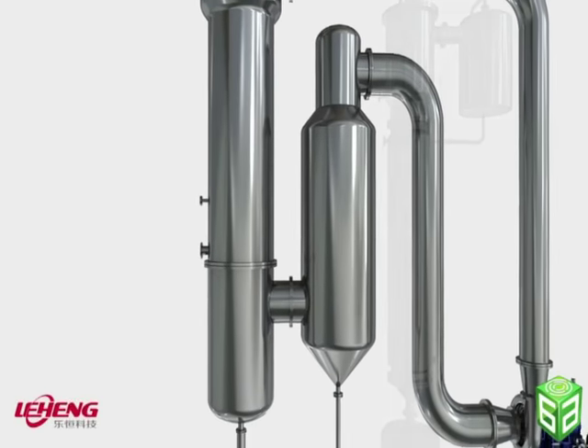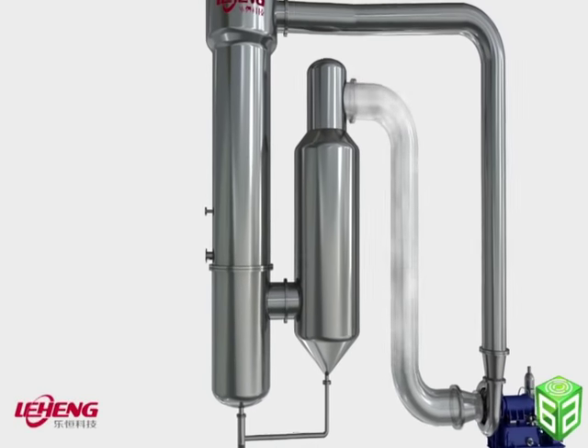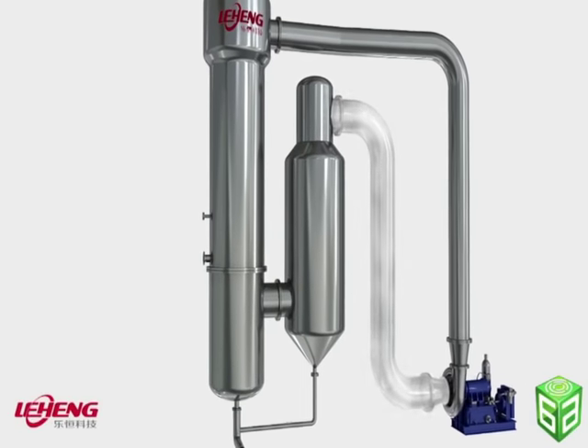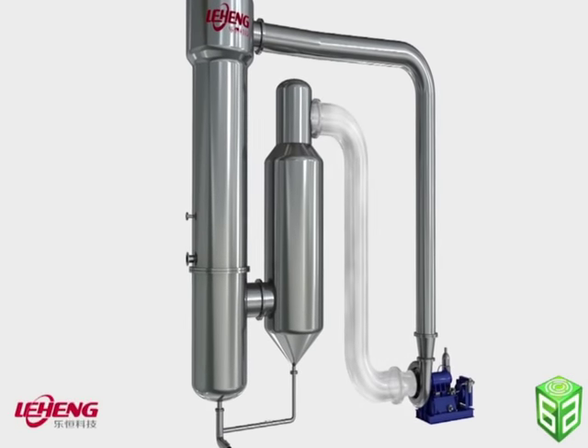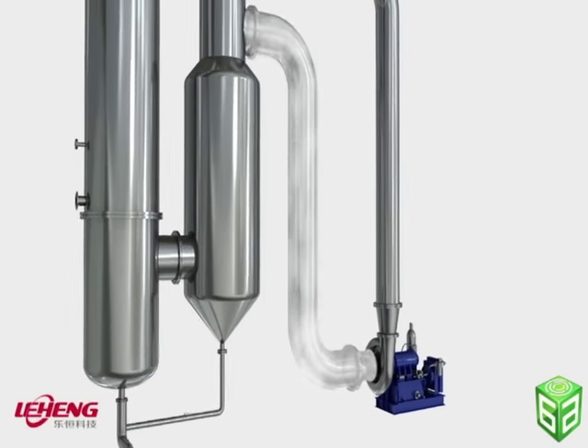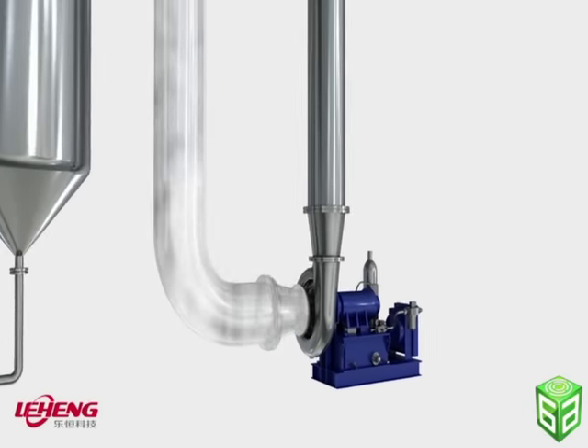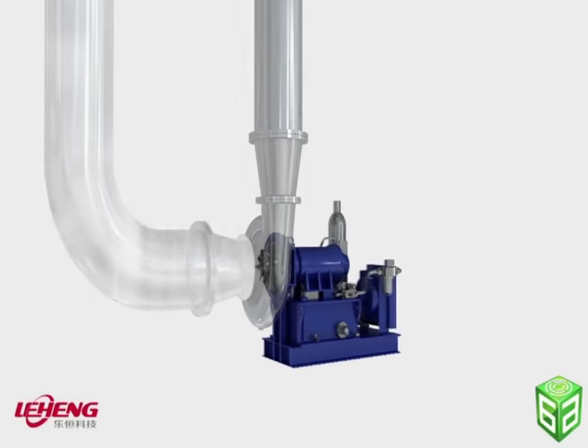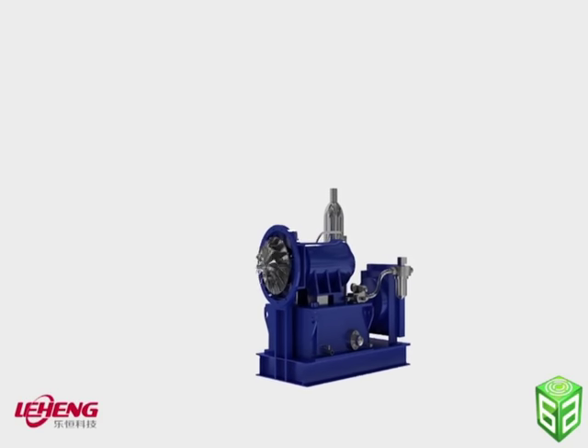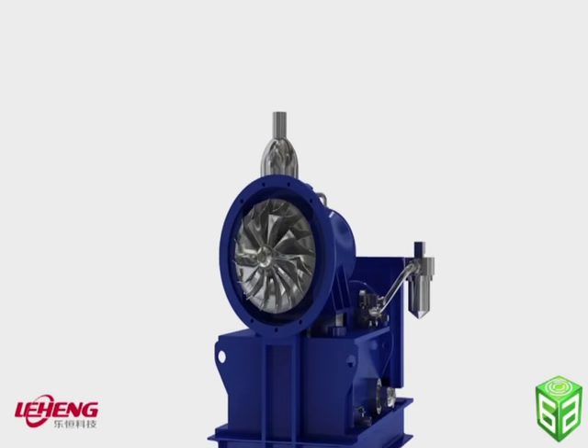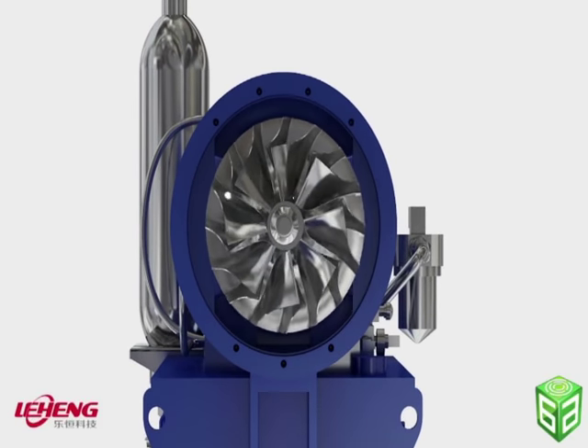Steam is generated through the liquid evaporation process and flows into the direct drive centrifugal steam compressor after leaving from the top of the separator.